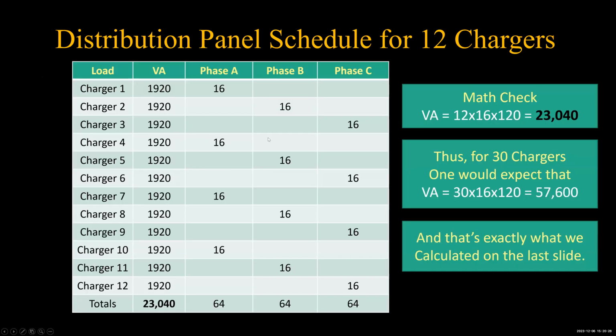And now, if we distribute it just like this on a panel, phase A gets the first one, then B, C. I only had room for 12 of them here, but notice we got 23,040 for 12 with 64 amps per phase balanced. And if we then extend that off to 30, with 30 of them, we're going to get 57,600. And that's exactly what we calculated on the last slide as how much power is available. So it would seem like this is all we have to do. It's just list phase to phase or phase to neutral. Well, it works fine for phase to neutral, but there's a little surprise on phase to phase, and that's what I want you to see.